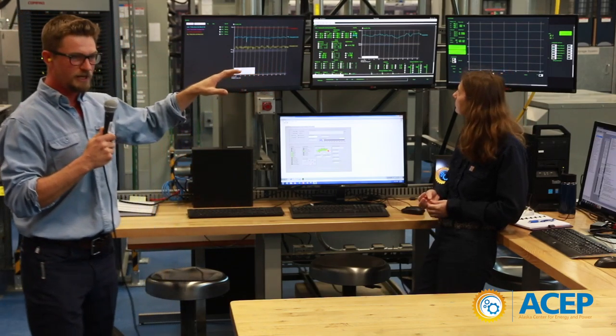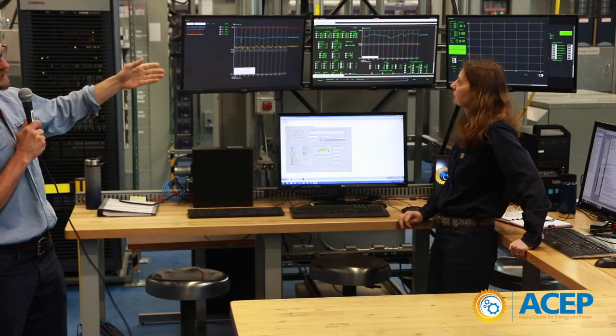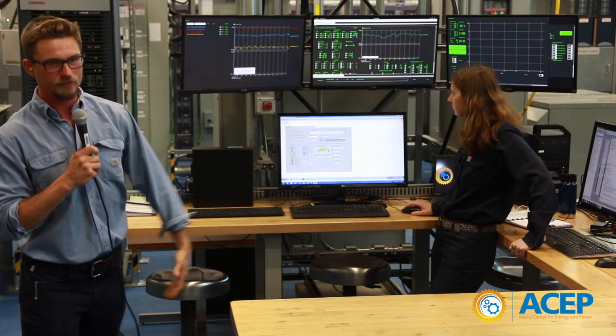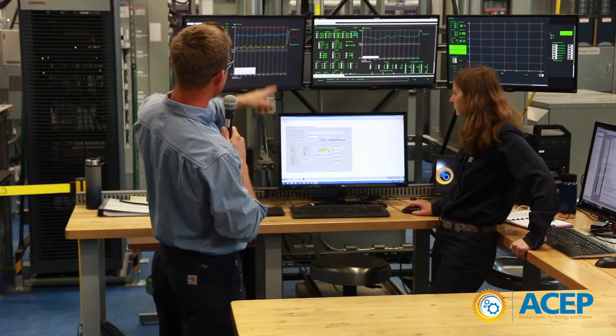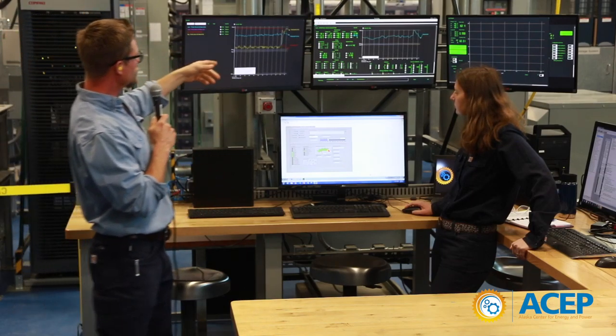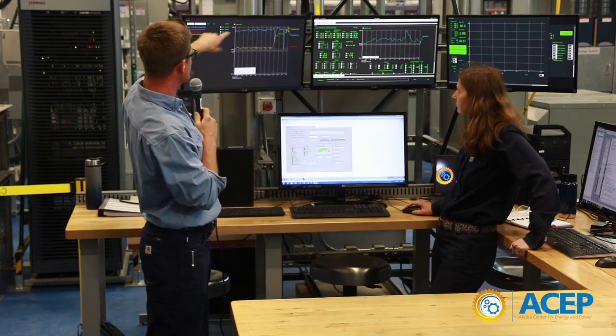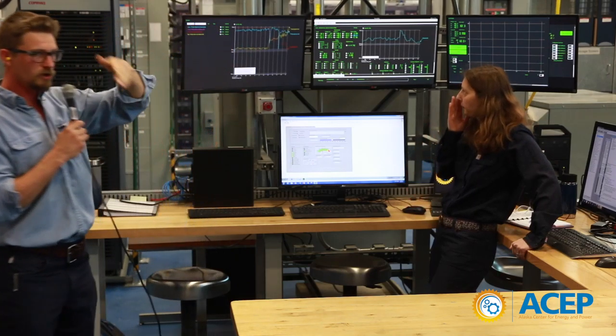It's not that big of a wind turbine, so we're not curtailing that much wind power. We're actually displacing quite a bit of our diesel fuel and we're really happy with how this wind turbine is working. So what do we do? We buy another one. Now we have 100 kilowatts of wind power. Ton is increasing our wind power — the yellow line shows wind power increasing. And what's happening to our red line, our generator? It's decreasing — the loading on our generator is going down.